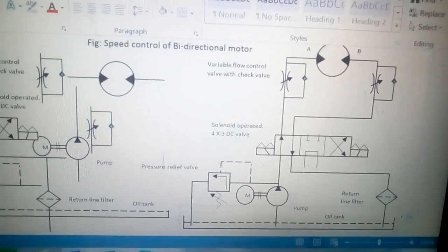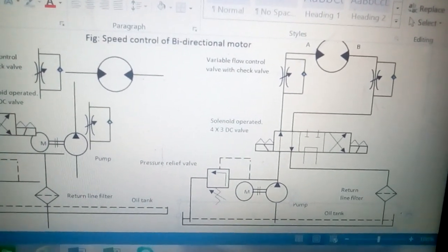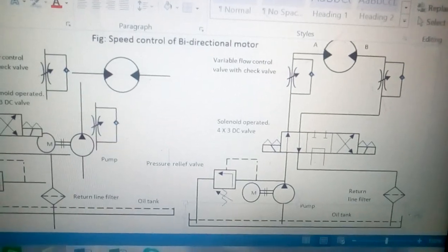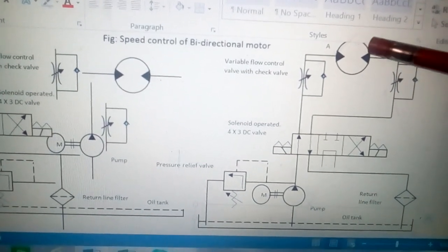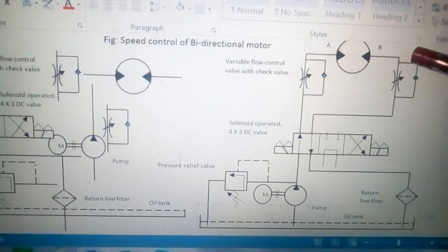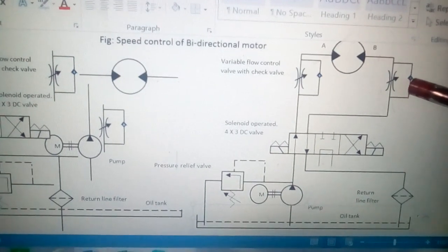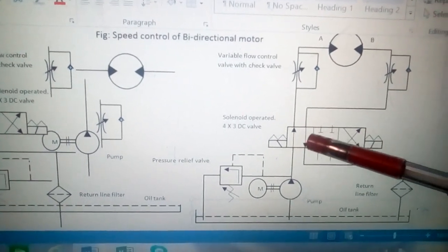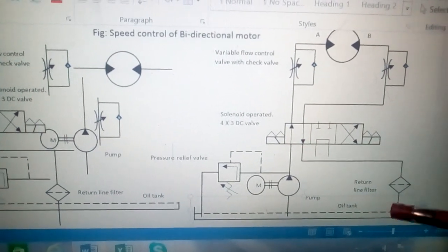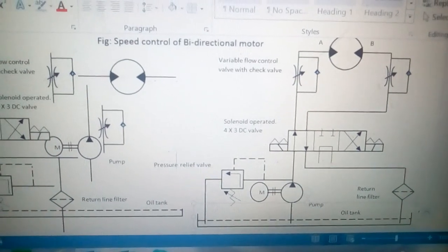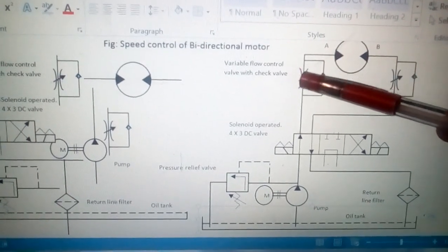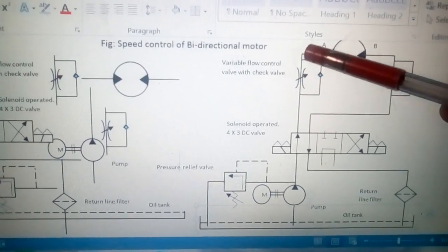In position one of the DC valve, pressurized oil enters the motor through port A and the motor rotates in the clockwise direction. The used oil comes out, does not pass through the flow control valve but passes through the check valve, then goes to the DC valve and returns to the oil tank via the filter. The speed of the motor is controlled by the flow control valve near port A.